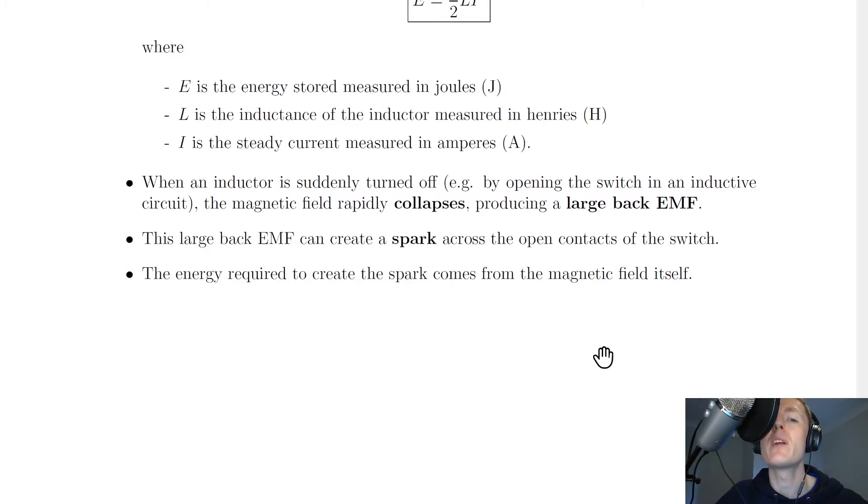And a very important thing to be aware of is when you're using inductors, when an inductor is suddenly turned off, for example by opening the switch in an inductive circuit, the magnetic field rapidly collapses, producing a large back EMF. This large back EMF can create a spark across the open contacts of the switch. The energy required to create the spark comes from the magnetic field itself.